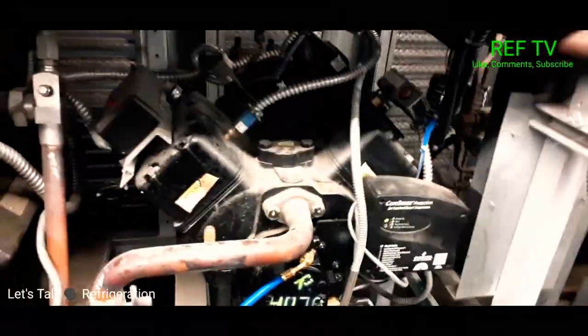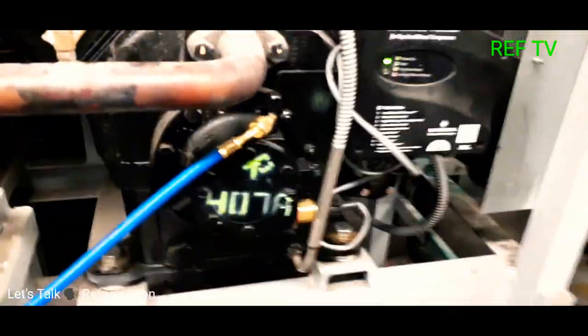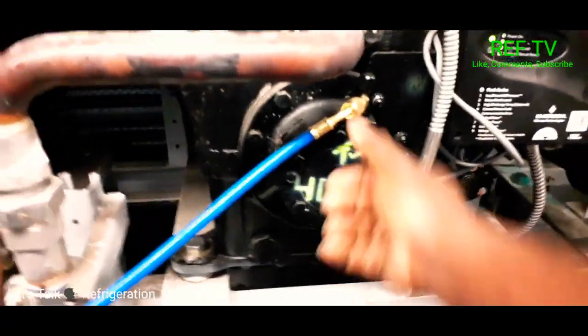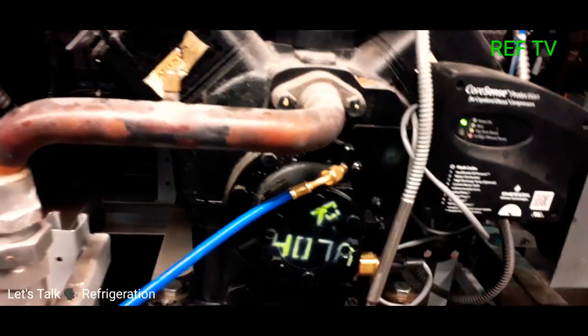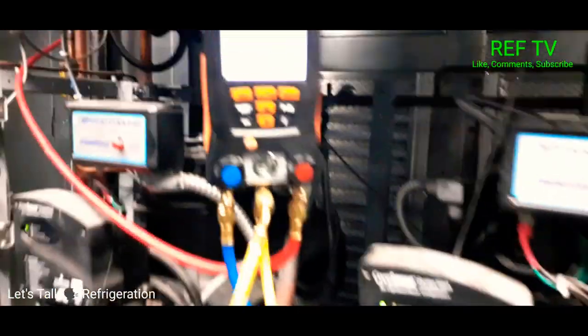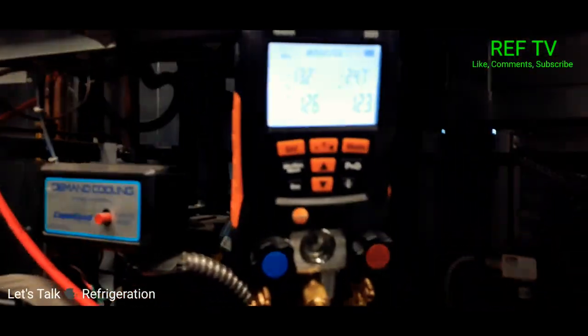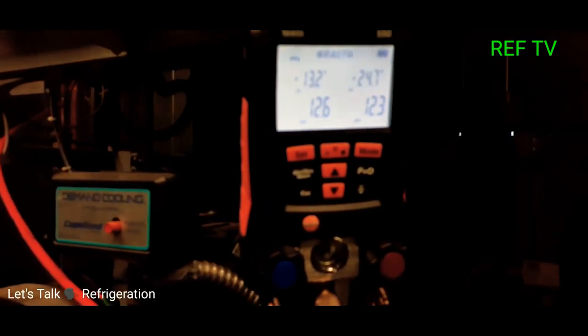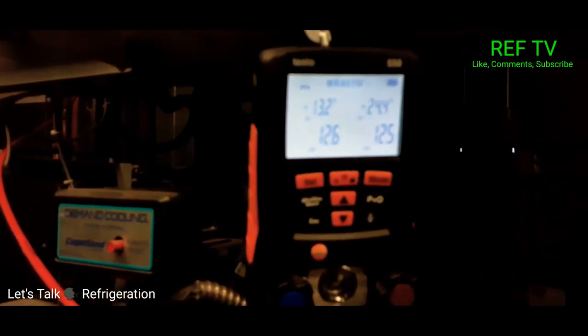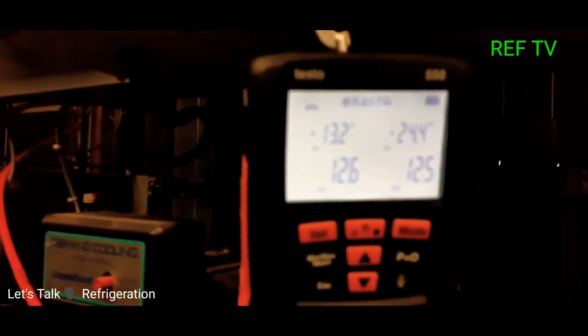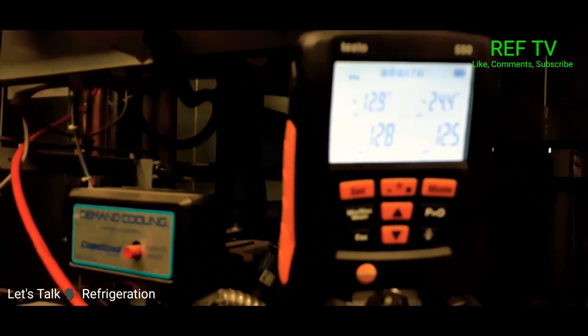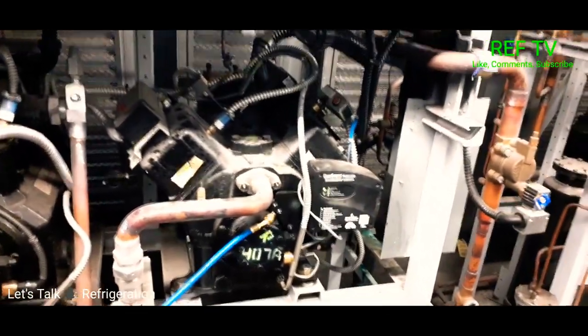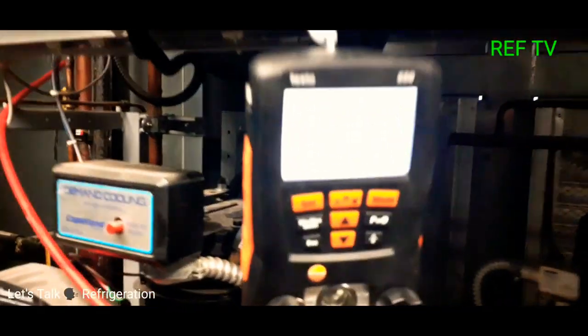All right, so this is compressor 3. This is the compressor that was tripped on oil. I'm hooked up here right to my oil pump, and basically gonna check our net oil pressure. So our suction pressure minus our net oil pressure, what are we seeing? 12 PSI. So we have no differential. So we got basically 0 net oil. We need to be at least 45 to 50 PSI differential across there. So right now we have no difference at all.